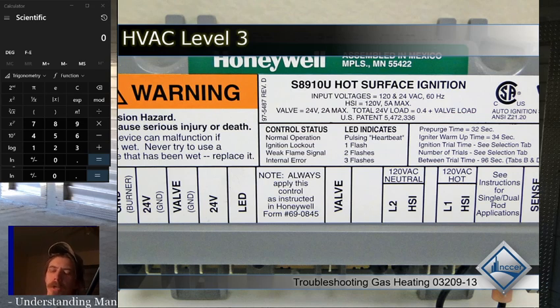So what you can do to test the thermistor is check the voltage before it and check the voltage after it. And if you're not dumb like me and you remember how to calculate your voltage drop, then you can figure out what the resistance is based on how much the voltage dropped. Otherwise, you can just take the thermistor out of the circuit and measure the resistance. First you'll make sure it's not open or shorted, so you shouldn't have 0 ohms and you shouldn't have infinity ohms. You should have something in between. Usually, if a thermistor's bad, it's open or shorted, so you'll get one of those.